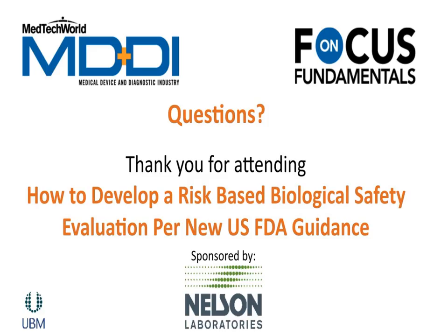Our first question for you, Audrey, is if I just follow the testing outline in -1, why would I still need to do a BER? That is a great question. So the testing outline in the -1 is good to follow, but if you noticed in the FDA guidance document, there were some of those categories that actually had zeros, so they have X's and O's. And those O's signify testing that may need to be addressed or they would like you to address.